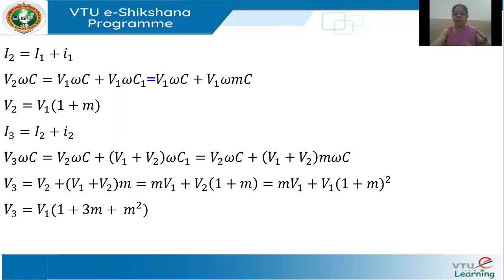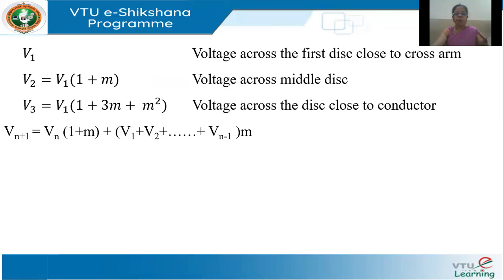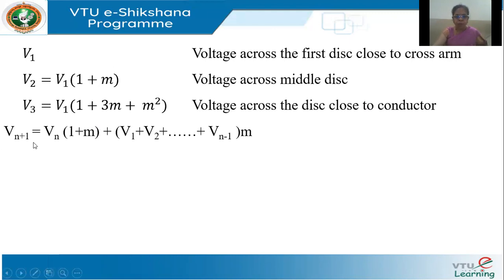To summarize: V1 is the voltage across the first disc close to the cross arm; V2 = V1·(1 + m) across the middle disc; and V3 = V1·(1 + 3m + m²) across the disc close to the conductor. For any arbitrary number of discs, the general recurrence is: V_{n+1} = V_n·(1 + m) + (V1 + V2 + ... + V_{n-1})·m.